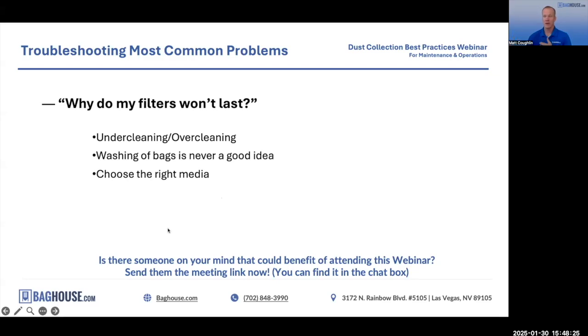If you're running 24/7, a highly demanding application, abrasive dust, all those things, they won't last as long. If they're sporadically used, light dust loading, they'll last a lot longer. But a general rule of thumb I like to say is about a year. It really depends on you, but people like to have a number to go by. So once a year is kind of a middle of the road estimate for how often you should change your filters.